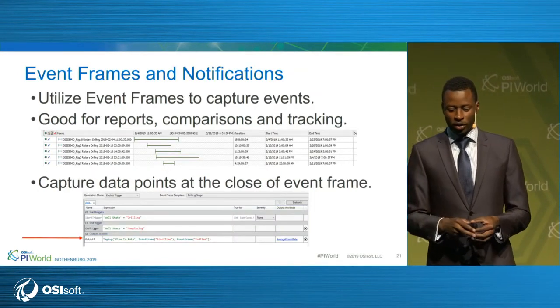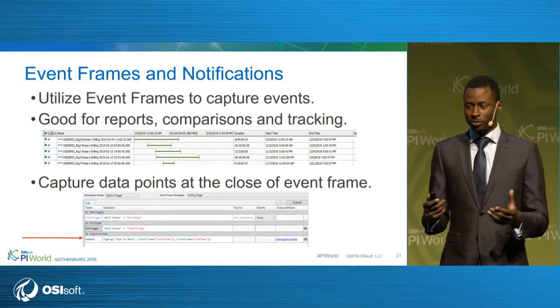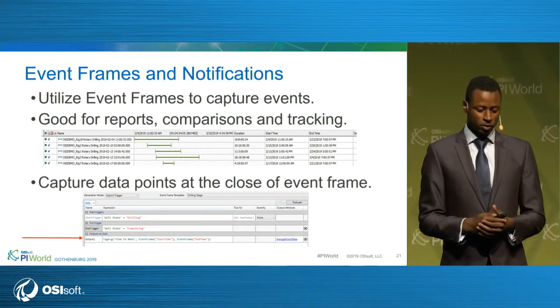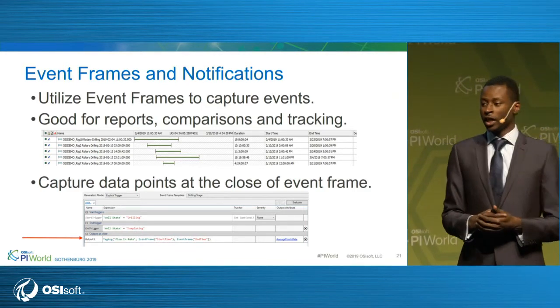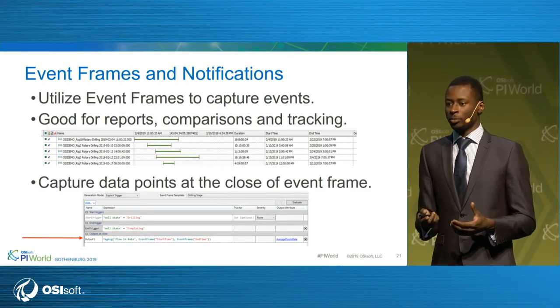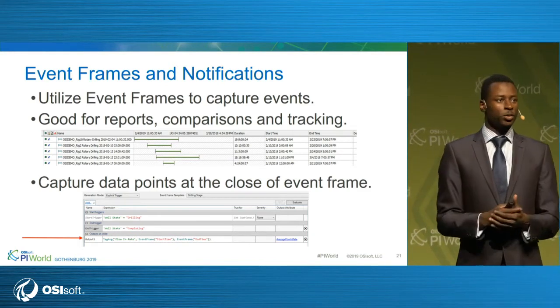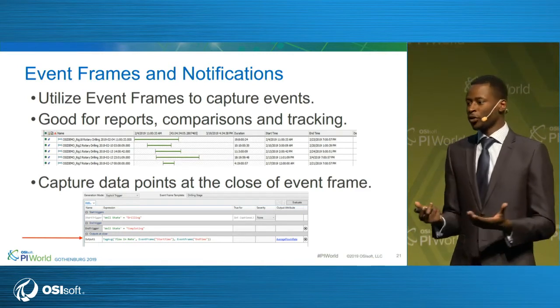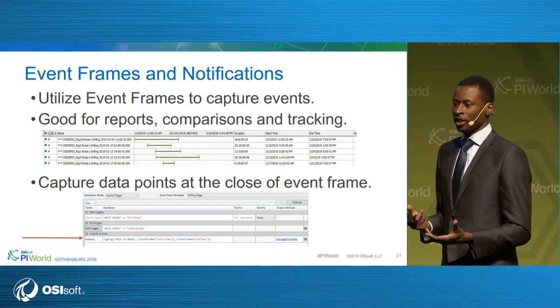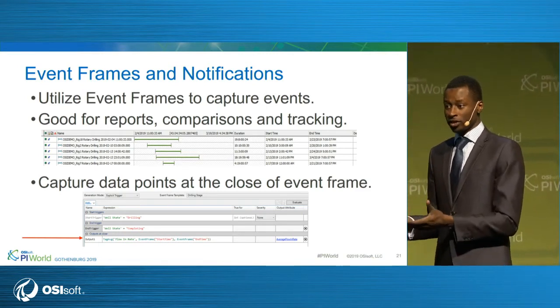All right, so a word on event frames. Event frames are really just specific segments of time which you should be interested in within your process. For example, maybe it's a pump which has just been started up. You want to see how your parameters are operating over that time period, right? So an event frame has a start time and an end time. And within this time, you can monitor those parameters.